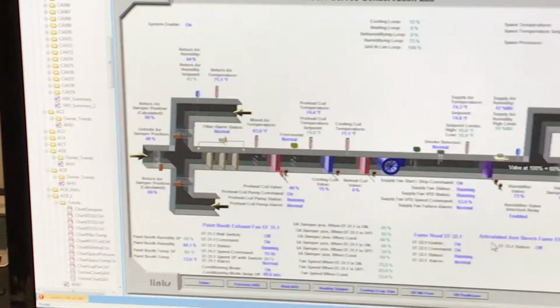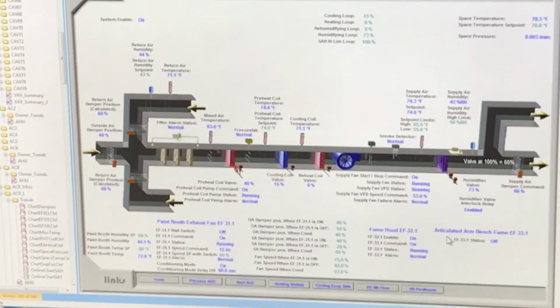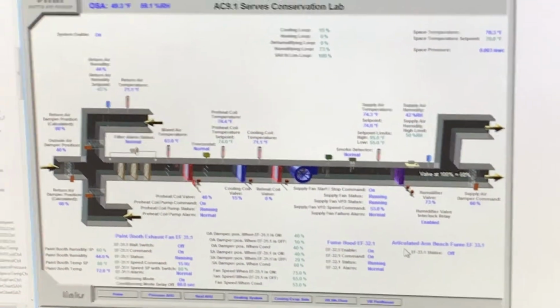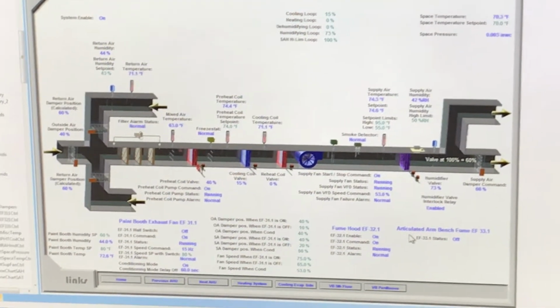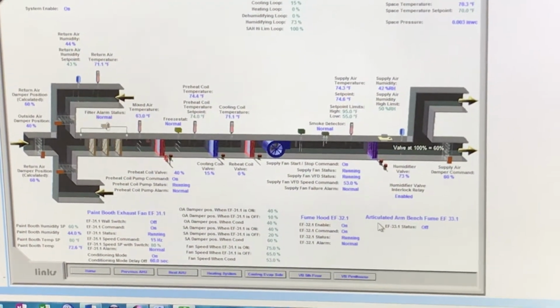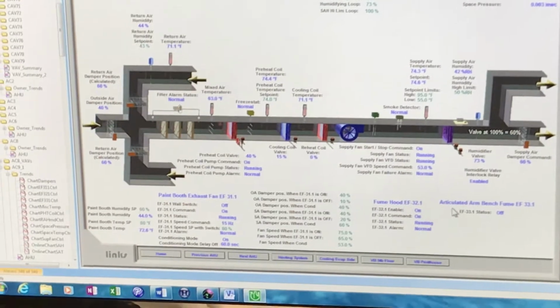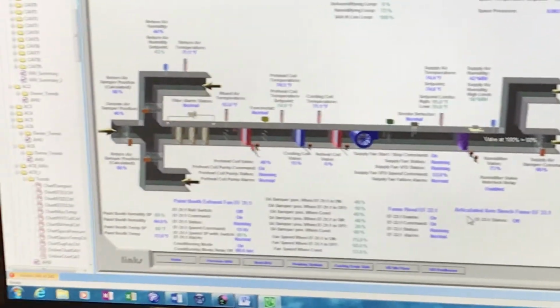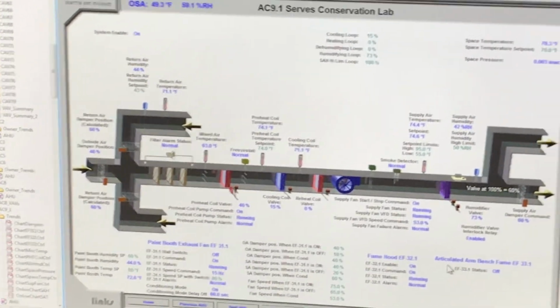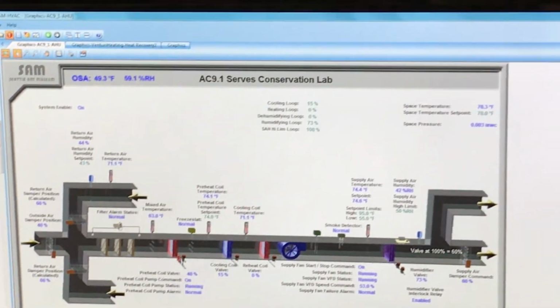The other thing is the steam valve. Even if it shows 100%, it's actually only going to be open to 60%. That's to stop excessive humidity dump into that conservation lab. At the valve itself, right? Yes, at the valve itself. So that way we don't have a sonic condition like we did last time it opened to 100%.